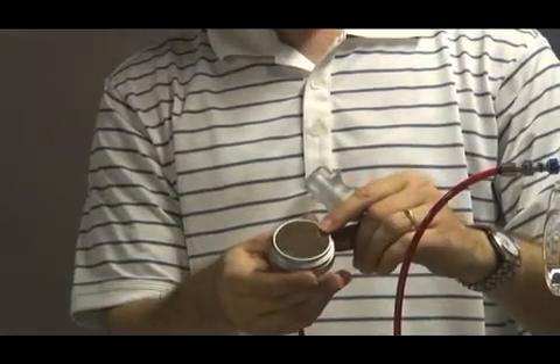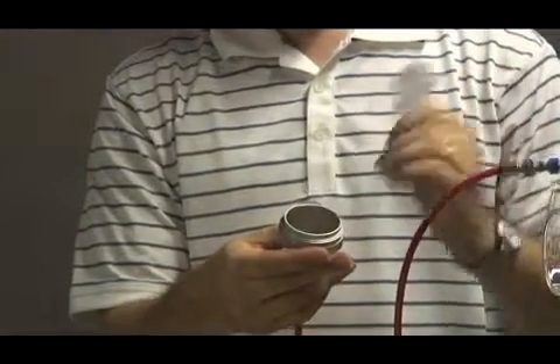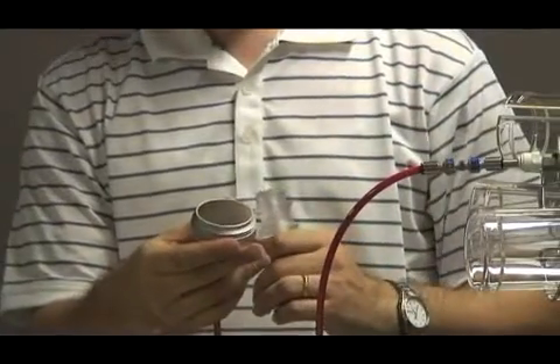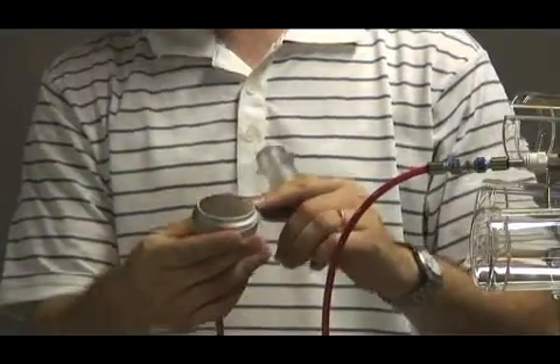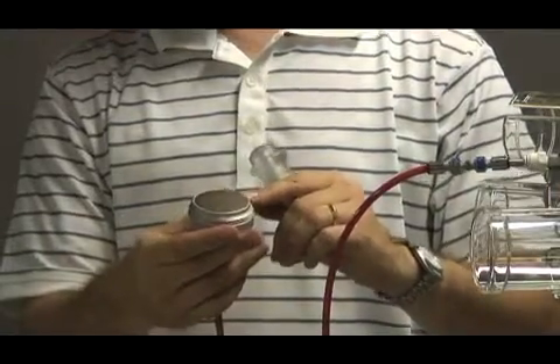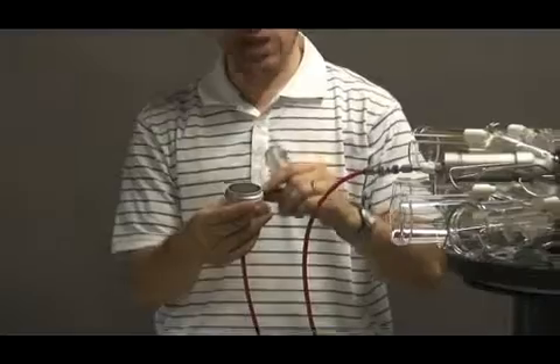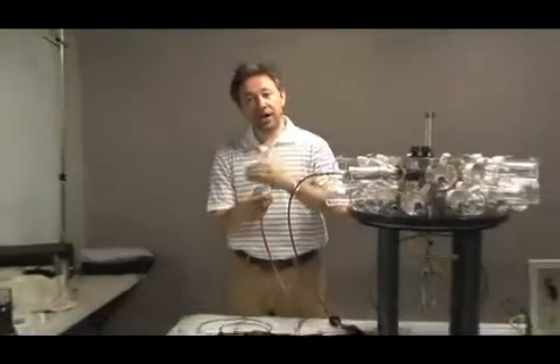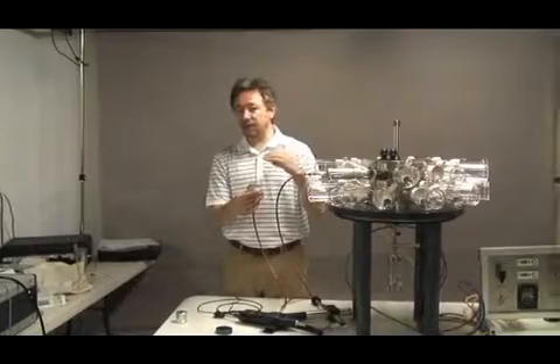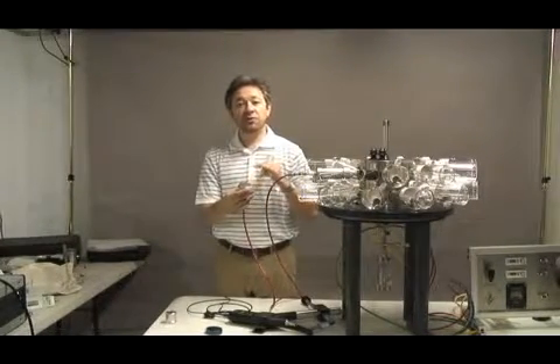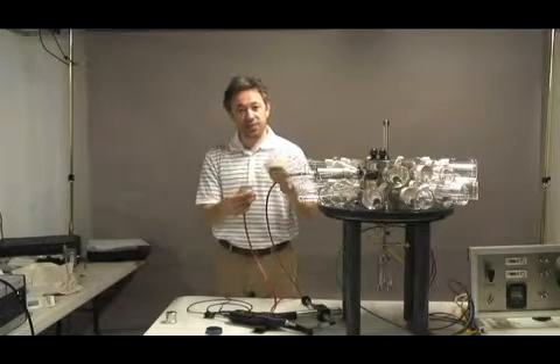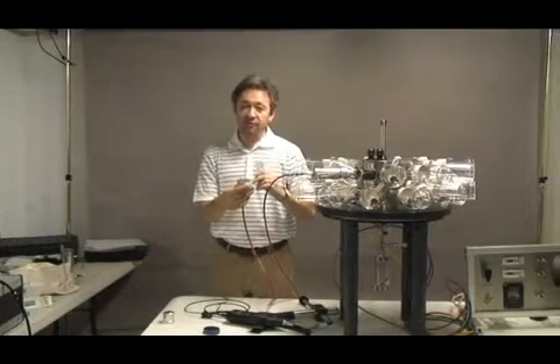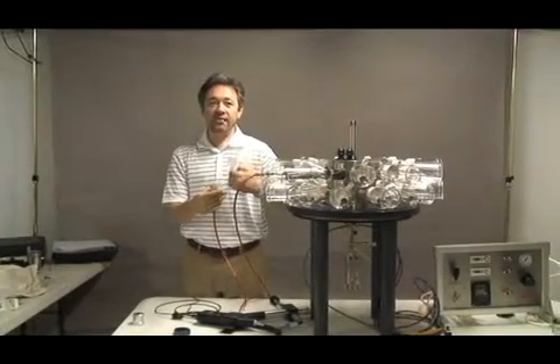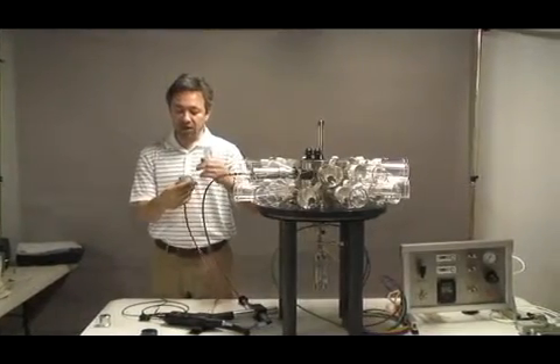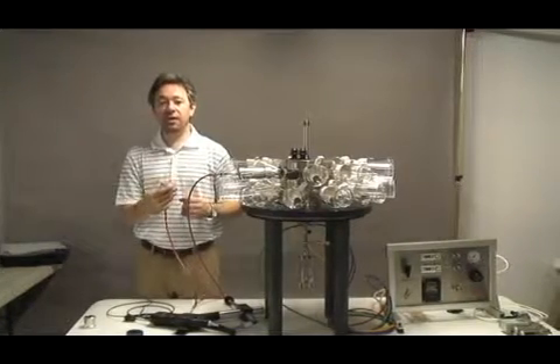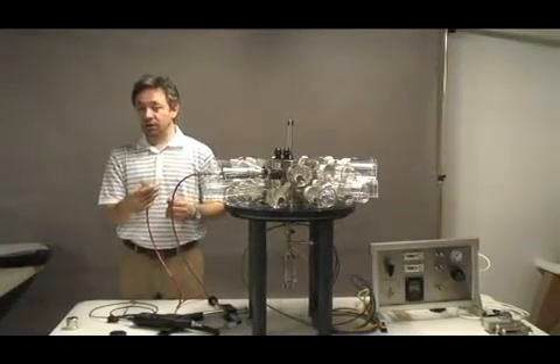And on the support screen, you will have the filter that you put in when you started sampling. Now the filter has to be weighed and conditioned before being put on the sampler. And once again, you put it back and condition it again. It has to have exactly the same temperature and humidity in both cases, before and after sampling. And the difference in weight, which is the weight acquired because of the aerosol deposition, will give you the concentration in the chamber.